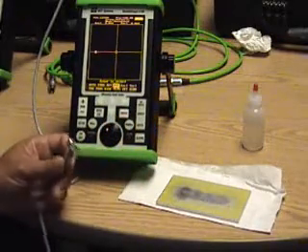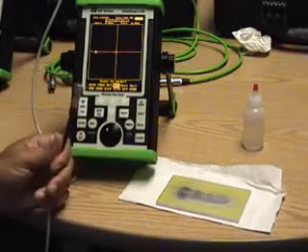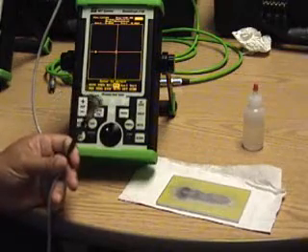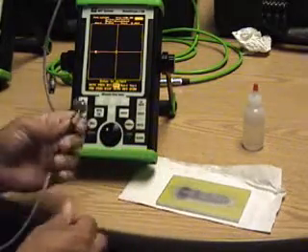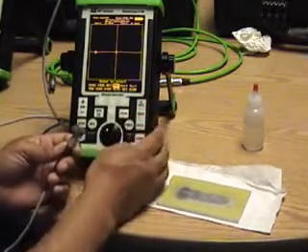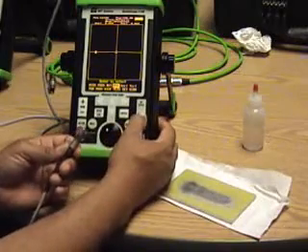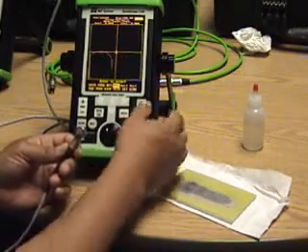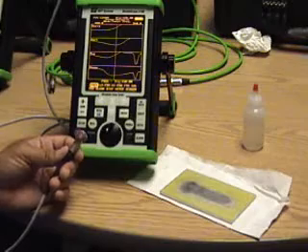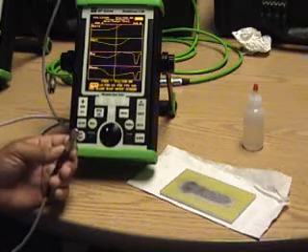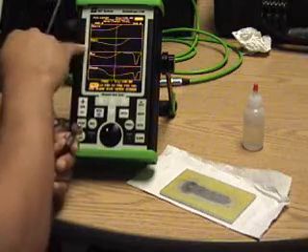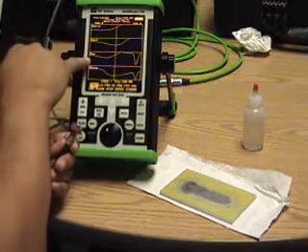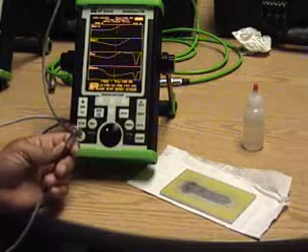Now, what I want to do is calibrate this screen. Basically, when I mean calibration, I want to find the resonance null point for the resonance probe. So we will press sweep and dots, and we see horizontal, vertical, magnitude and phase components of the signal.